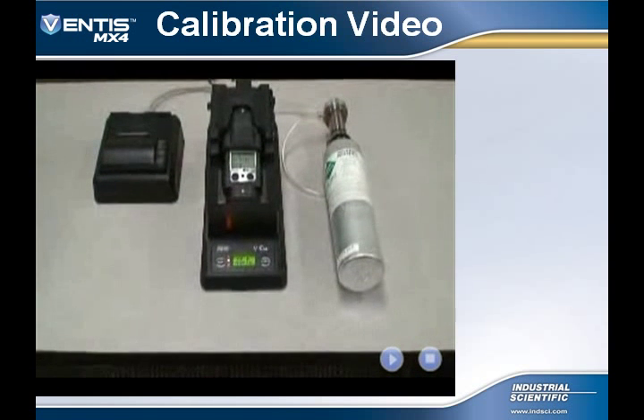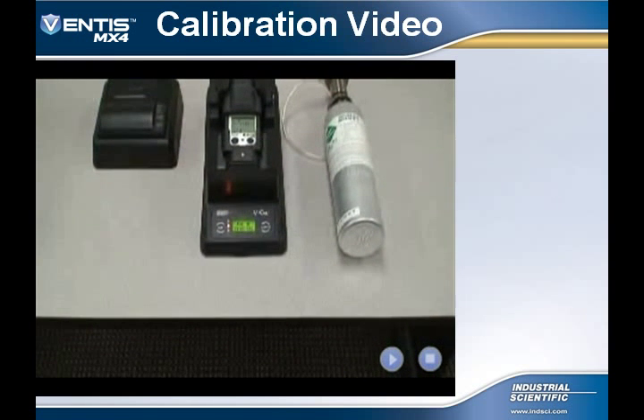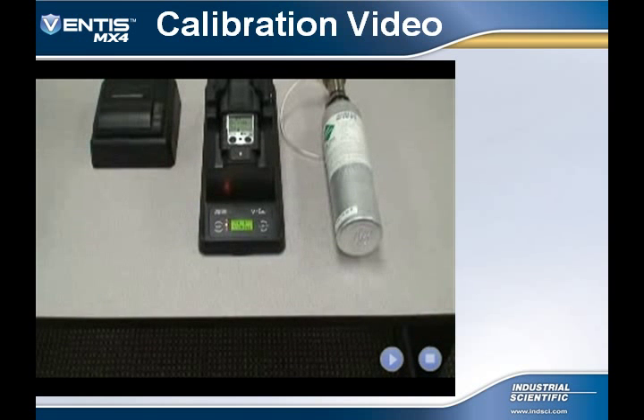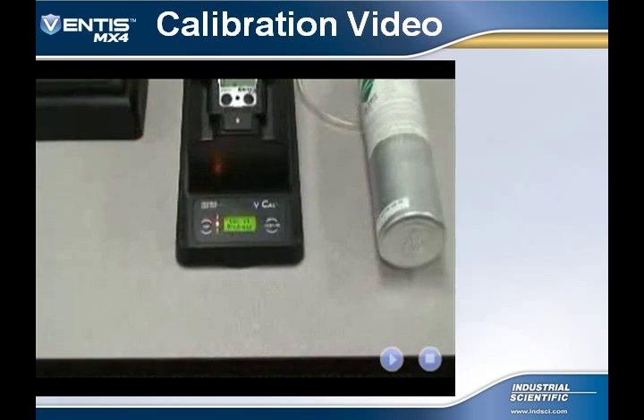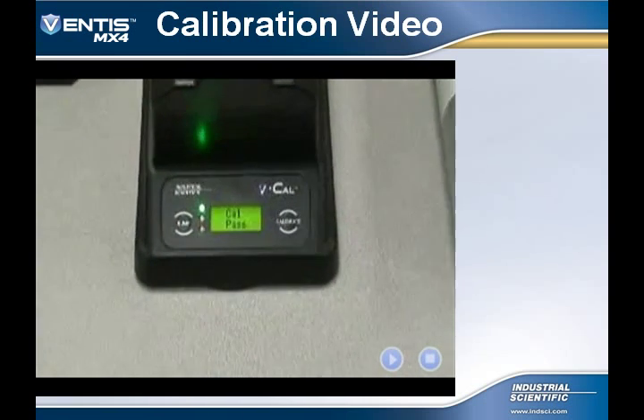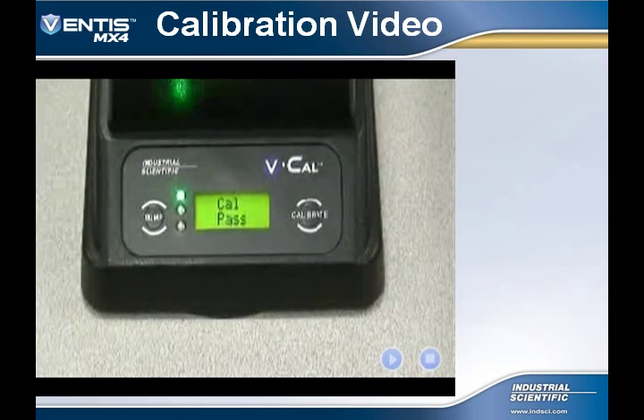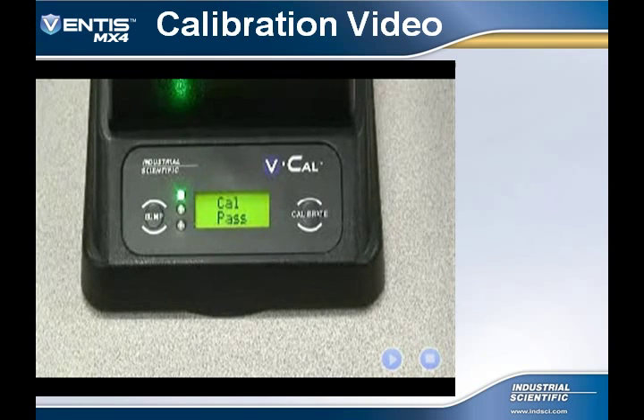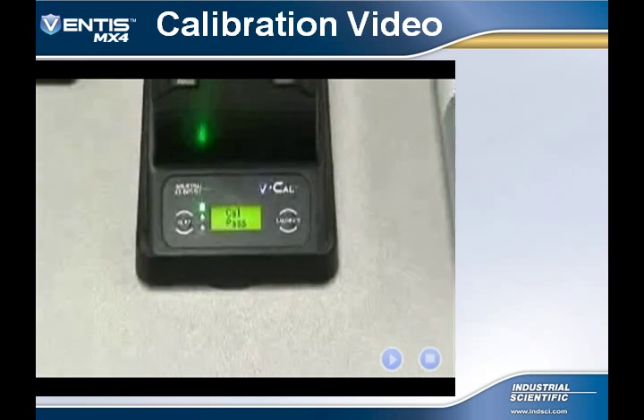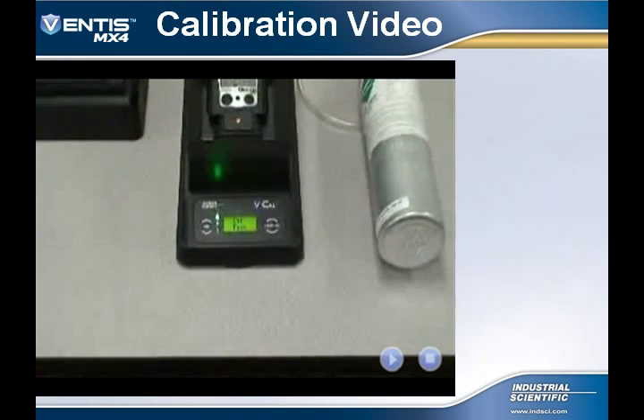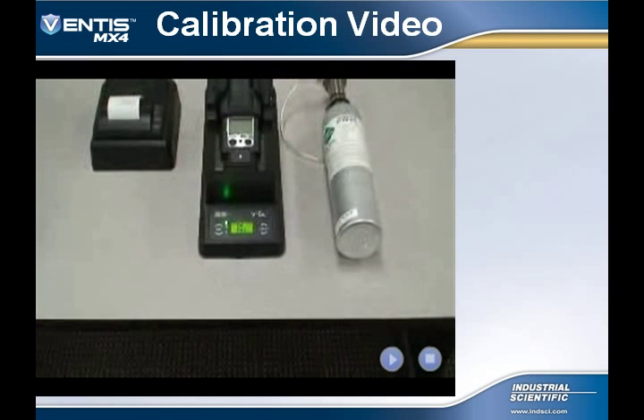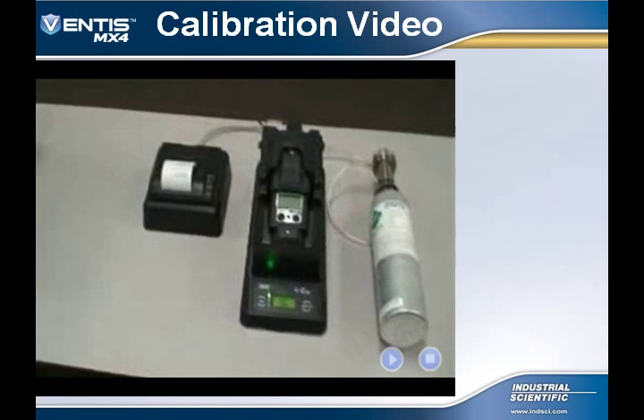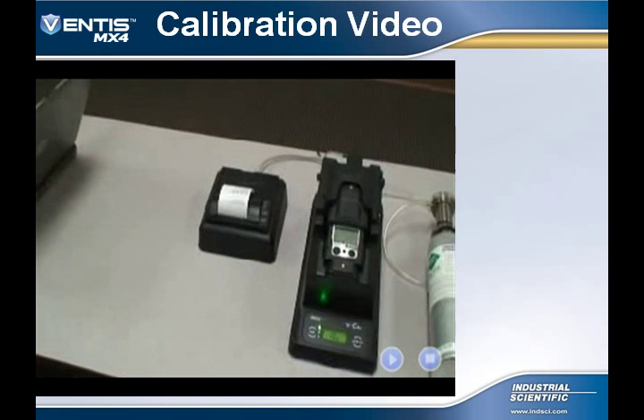Once the calibration is completed, a successful calibration will display a solid illuminated green LED with the VCal's display showing pass. If any of the sensors failed their calibration, then a red LED will be illuminated with the VCal's display showing fail. At that time, a corrective action will need to be accomplished. A printer may be connected to the VCal. A hard copy of the results will be printed from the printer.